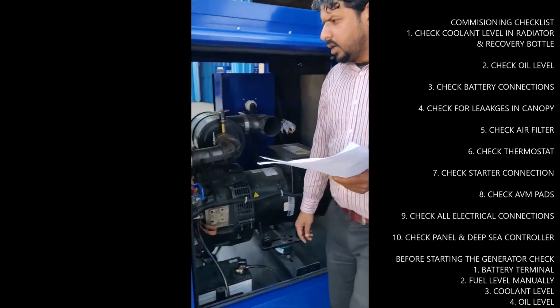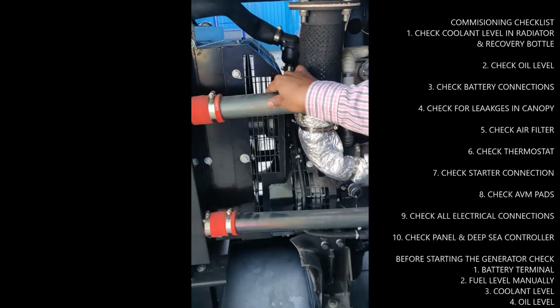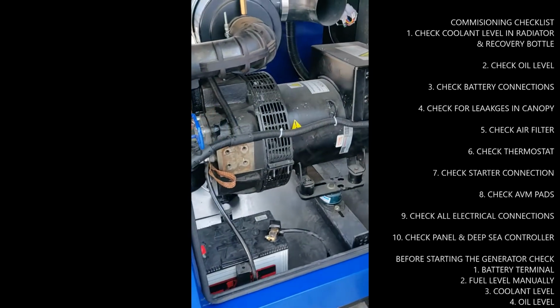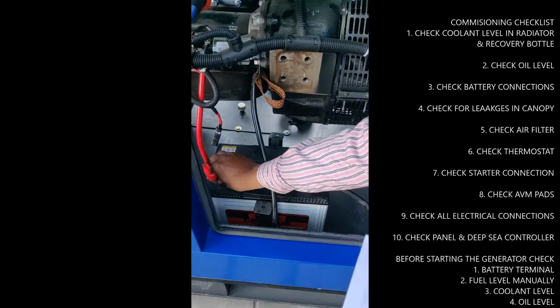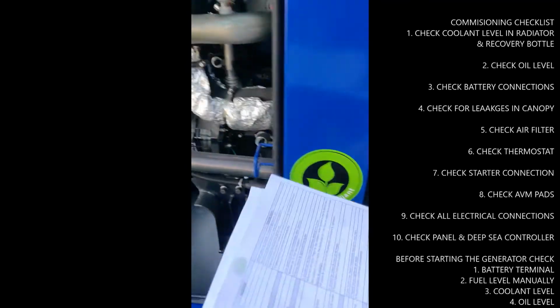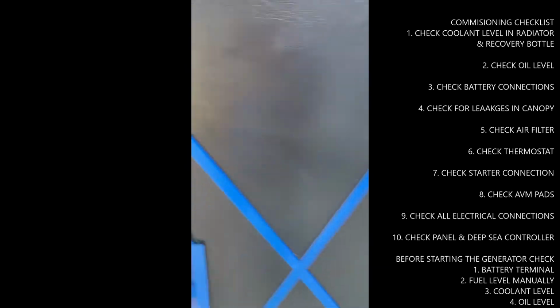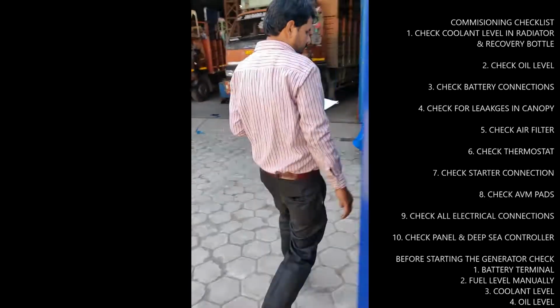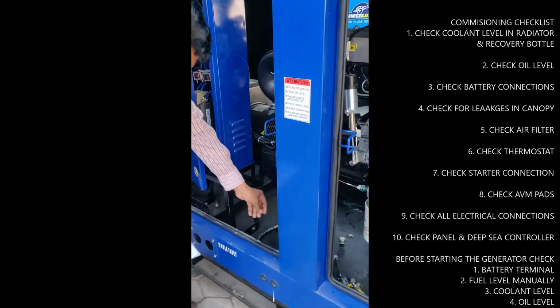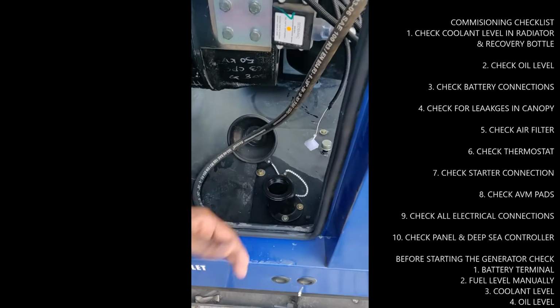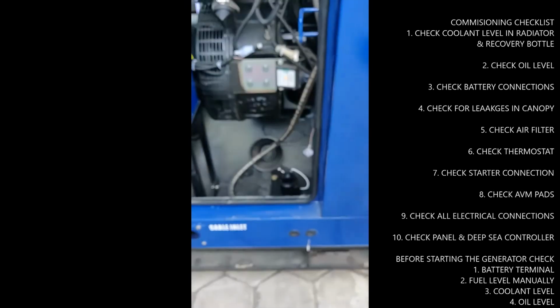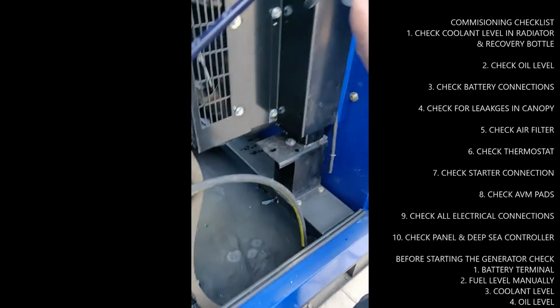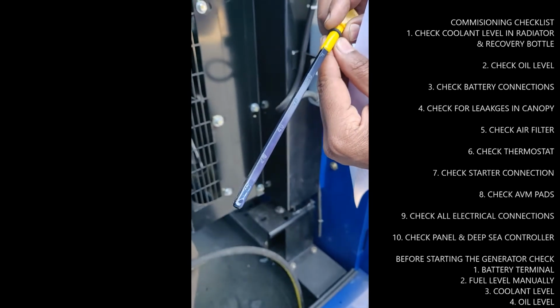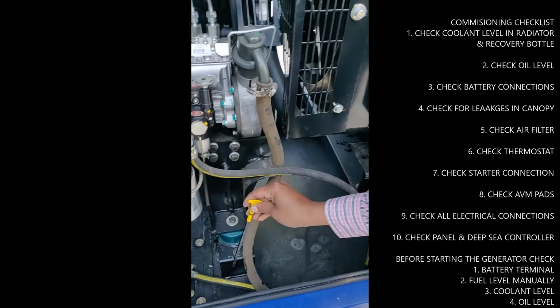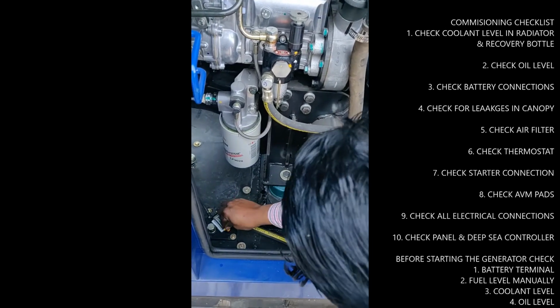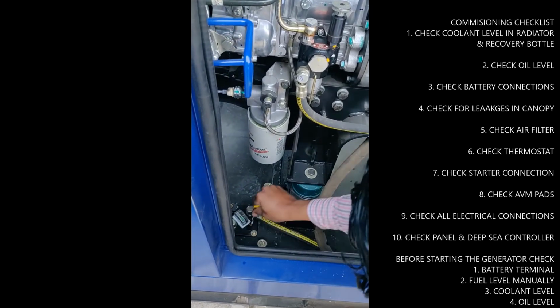Now before starting the generator, check the battery connections, the positive and the negative connection. Check the fuel level manually. Please make sure that the genset has fuel all the time and does not run on low fuel. You can check the fuel level from the manual dipstick. As you can see, this is the manual dipstick. In case the panel is not working, you can check the level of diesel from the manual dipstick like this.